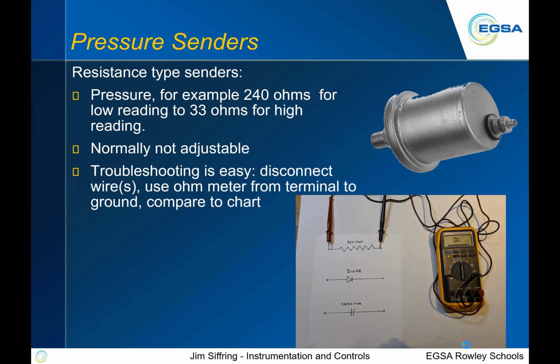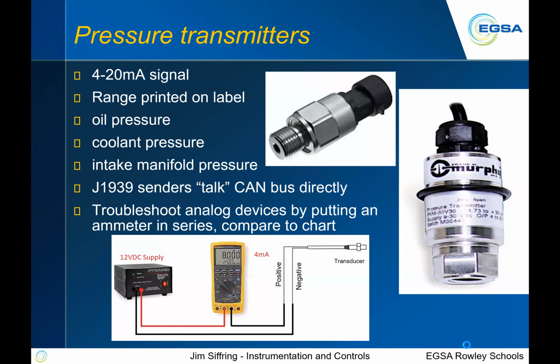Most often, if something's gone bad, you put your ohm meter on there and you just see an open or a short, and that it's bad. So pressure transmitters, typically something like this will give you a 4 to 20 milliamp signal. We'll talk a little bit more about 4 to 20 milliamp signals as we go through here.